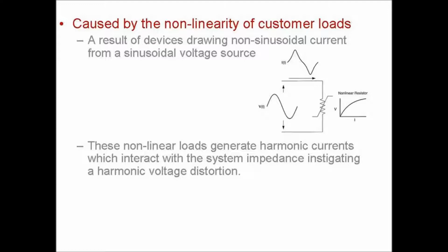And it draws load in a non-linear way, which the current will interact with and give you a distorted waveform. So you see that the top current waveform is not the same as the sinusoidal voltage waveform. So that's basically what causes a harmonic current to be on the system. And this occurs at various frequencies up and along. The problem is that these harmonic currents then interact with the system impedance, and that gives you a harmonic voltage distortion at various frequencies. So that's the fundamentals of it.